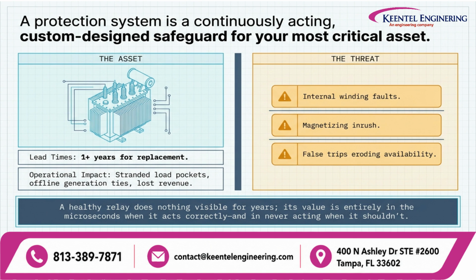The second is magnetizing inrush. Inrush occurs during transformer energization and can produce very large currents that may resemble an internal fault to a simple differential protection scheme. And the third threat is false tripping. An unnecessarily tripped transformer can reduce system availability even though no damaging fault exists.